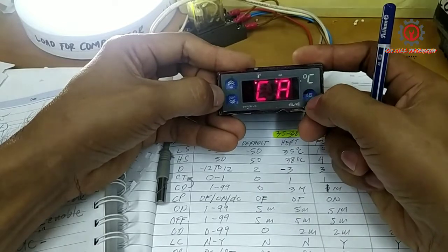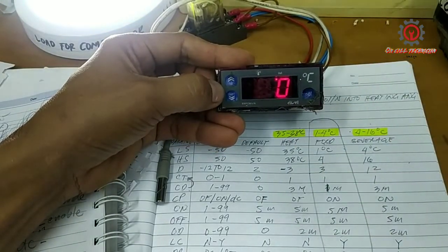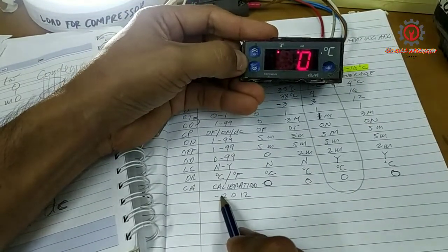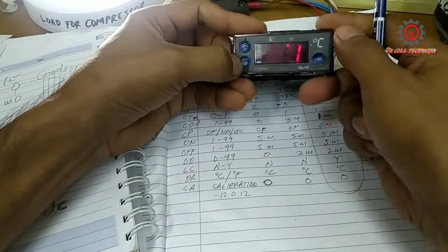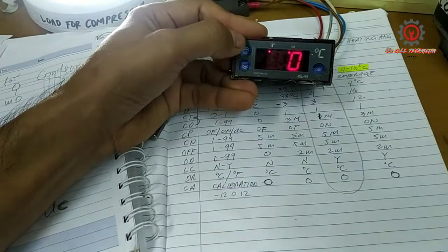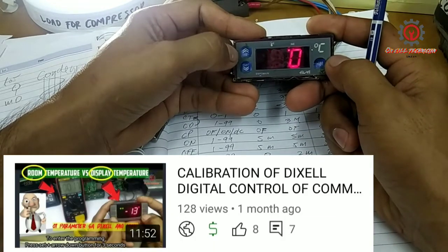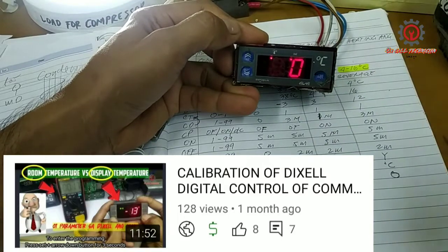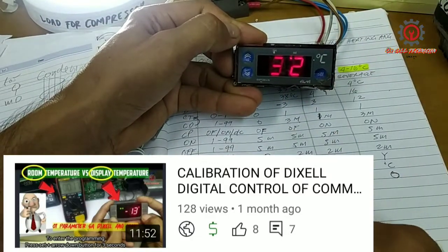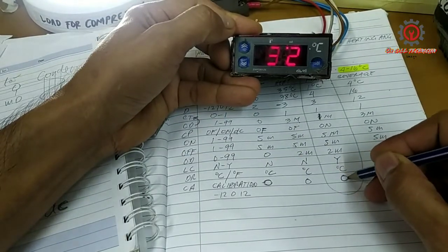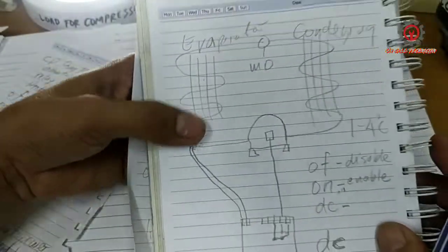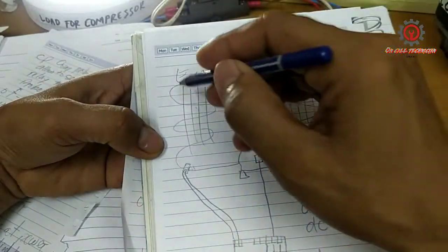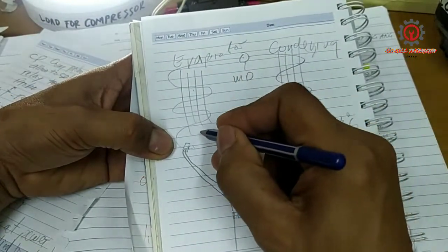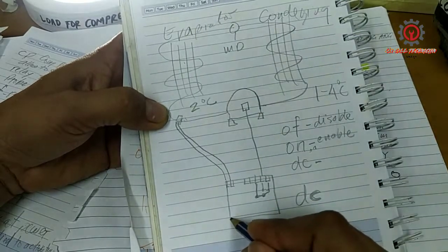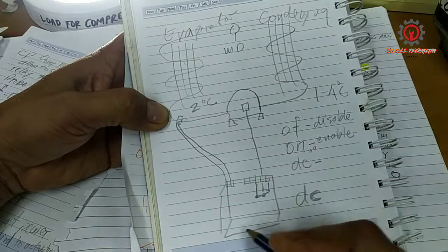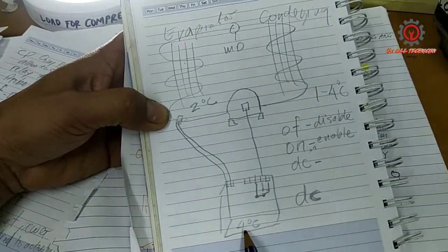CA, guys, is the calibration, and the range for the calibration is from negative 12, 0, 12. I elaborated on this, guys, in my Dixell video, so I'm going to paste the link and just watch it on how to do the calibration. Okay, for a brief explanation: calibration, guys, just in case this is your evaporator, the evaporator reads 2 degrees Celsius, while here in our control it only reads 4 degrees Celsius, so we have a differential of 2 degrees Celsius.